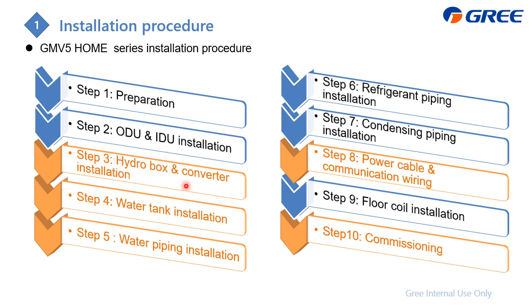After that is to install the hydro box or the converter, and then install the water tank and also the water piping system. After that is the regular part, which is the same as the heat pump VRF: the refrigerant piping and also the condensing piping. After that is the power cable and the communication wire, and then to install the floor coil. The last is to do the commissioning. This time, we just focus on the orange color, how to install it.